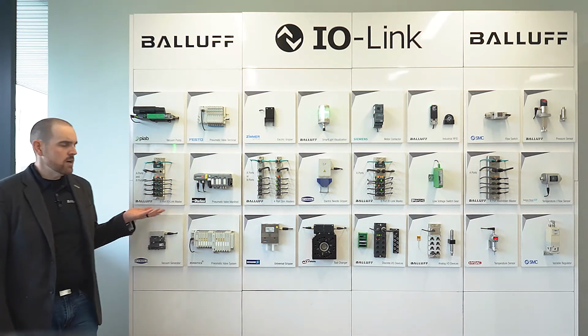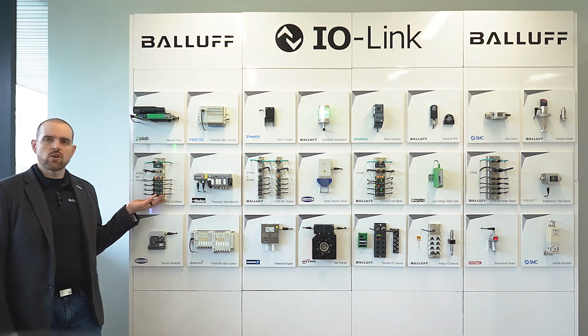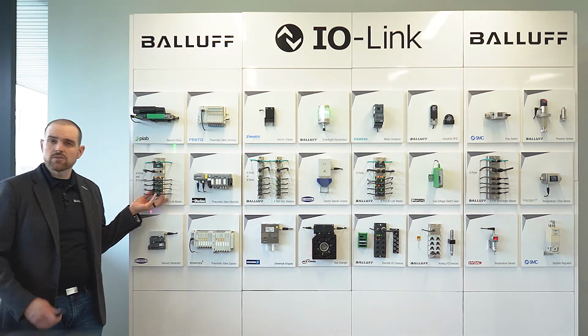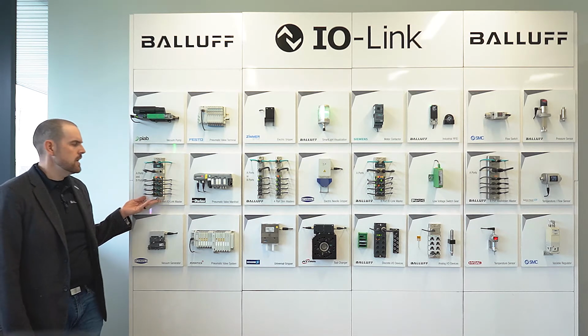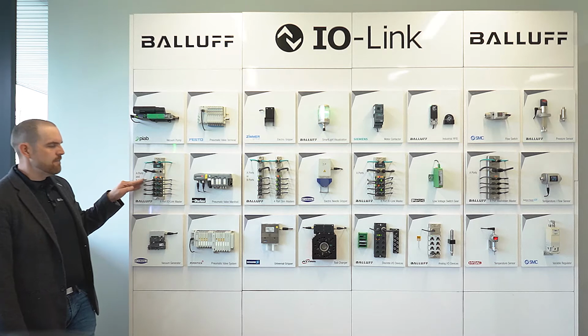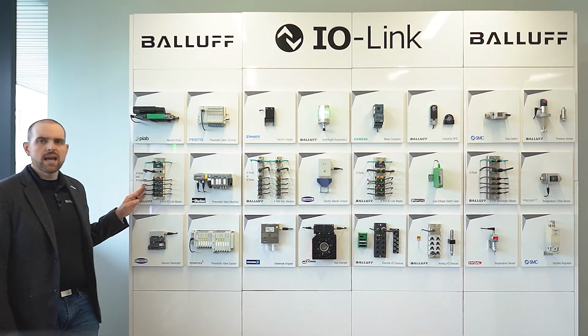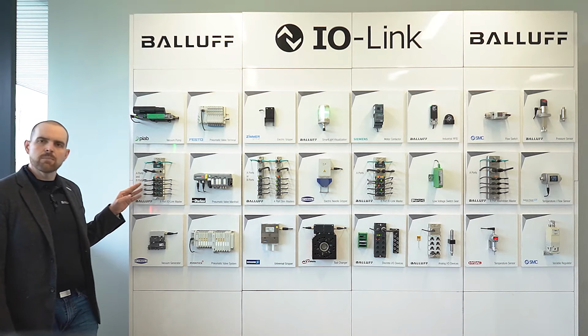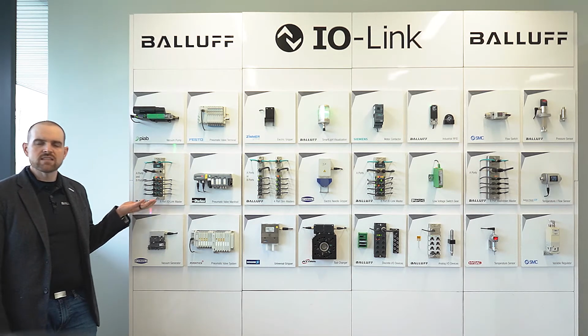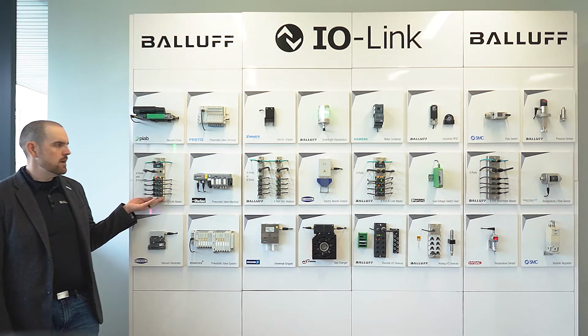These masters are machine mount I/O blocks available in many varieties. This one here is an 8-port version. We usually talk about the number of ports because that tells you how many IOLink devices you can connect. This 8-port version has the top 4 ports as A ports and the bottom 4 as B ports, so you can have a combination of input and output style devices all in one master block.